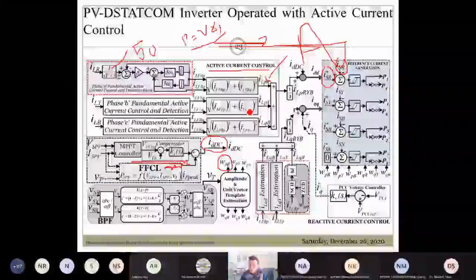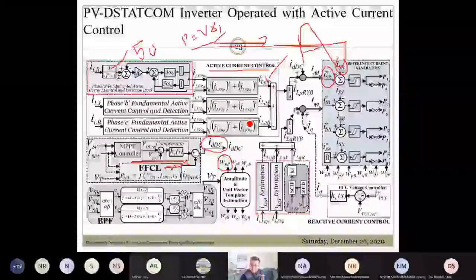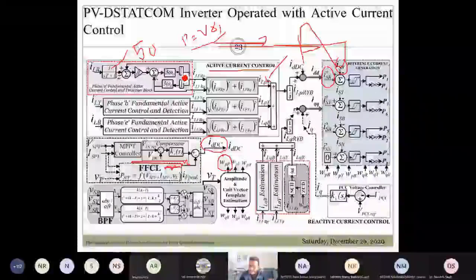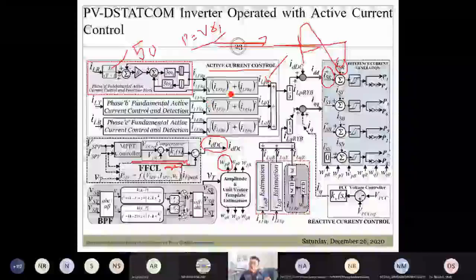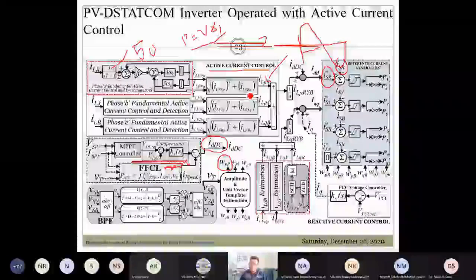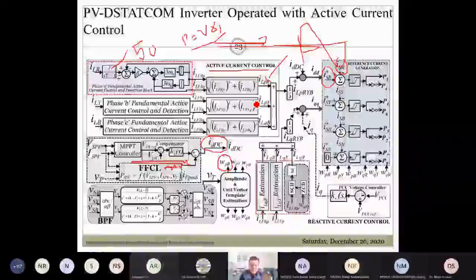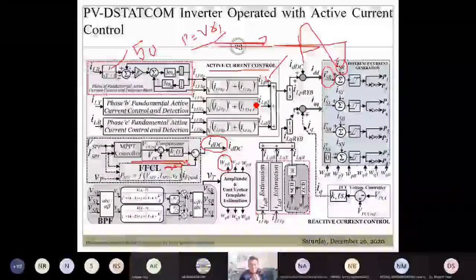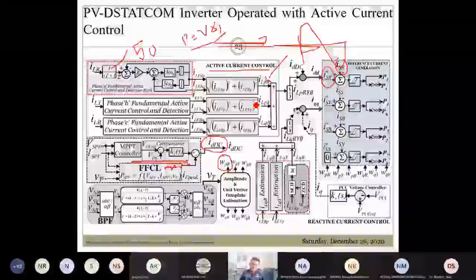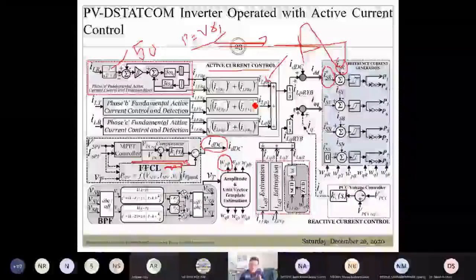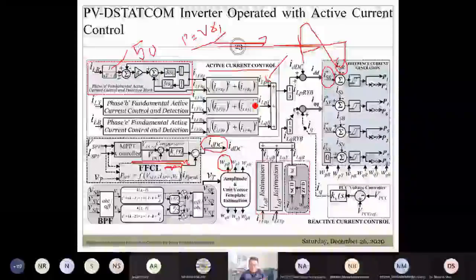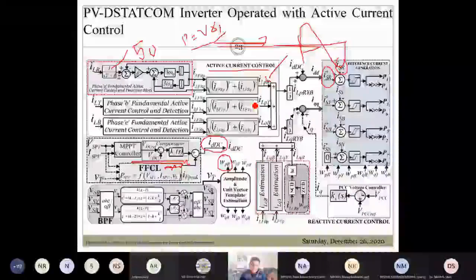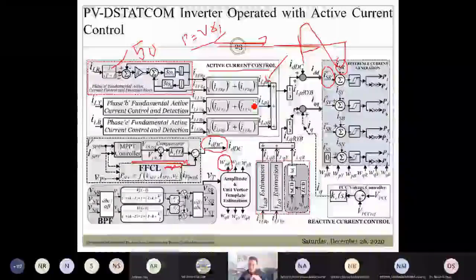But one more thing I would like to mention is that if the change in the voltage is prohibitively high, and the system cannot provide that much reactive power support, then the inverter is asked to stay connected but not inject any reactive power into the grid. In that case, the inverter stays connected, but it will not inject. It means the reactive power output of the inverter is 0.